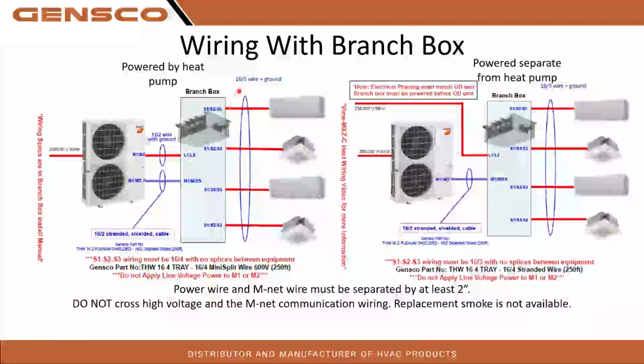New equipment, the Smart Multi, recommends 16.3. If you can run 16.3, I would highly recommend you do. But if you've got an older system that you're doing work on and they have 14.3 on there, I probably wouldn't go tearing up the house just to replace that wire. 14.3 seems to work okay. But if you are able to replace it, it may not be a bad idea. So that's from the branch box to your indoor equipment.